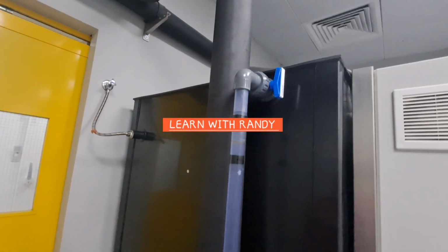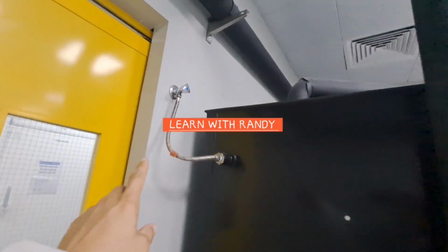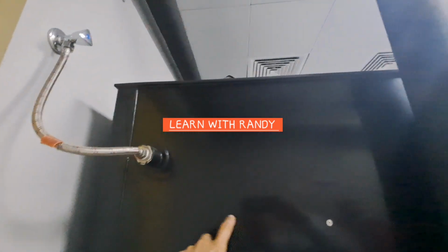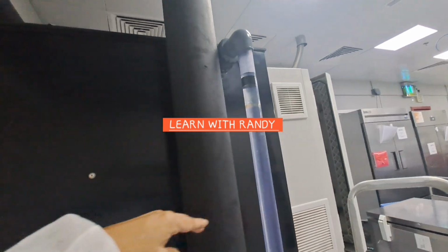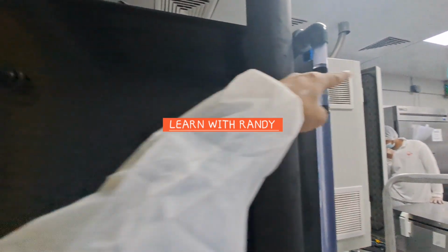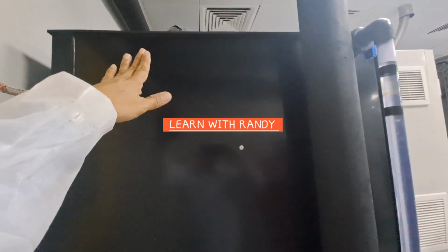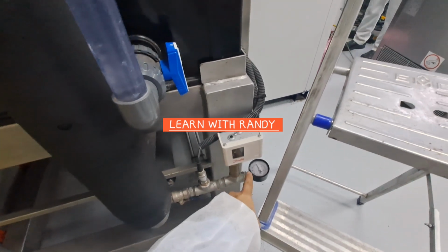So the water is transferred here, cooled by the fan, and then goes back to the heat exchanger. And this is for the refilling of water to the tank. Basically inside here there is a float ball. If the water level is low, the float ball opens and the water will refill until it reaches the maximum level. When it reaches the maximum level, the float ball will close, and the water will not flow inside. This is for the pressure, pump pressure.